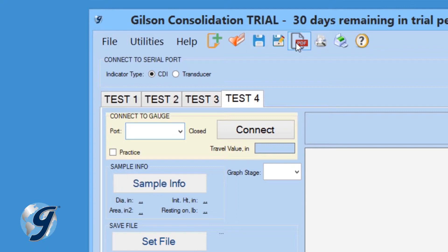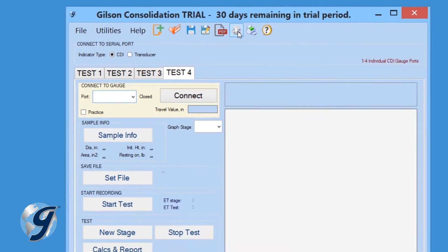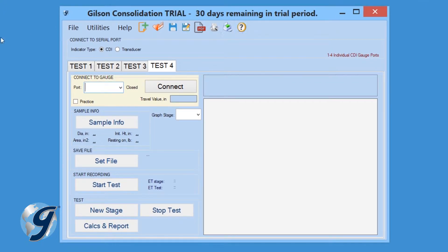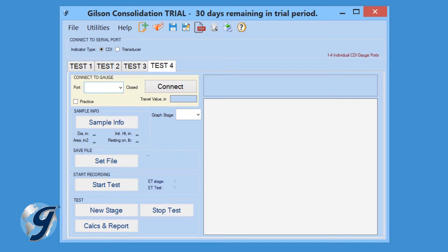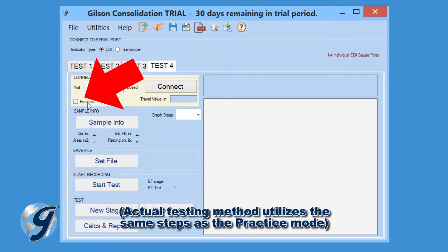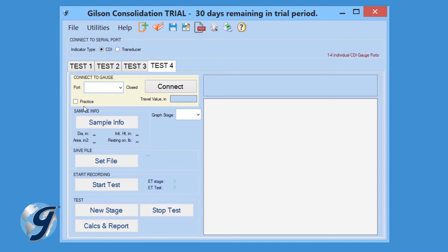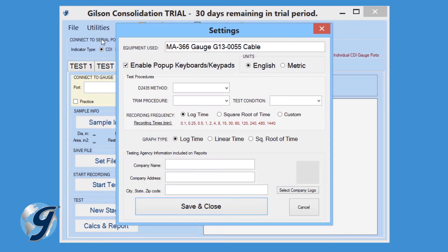At the top you will also see Program Command icons. Now that we have reviewed the menu bar, let's demonstrate how to perform a new consolidation test using the Consolidation Test Data Acquisition Software. For this demonstration we're going to use the software's Practice feature — more on that later. Make sure the computer is connected to the readout box or the digital dial indicator through its mini USB port. Click on File and New to begin the process, then click on Utilities and Settings.